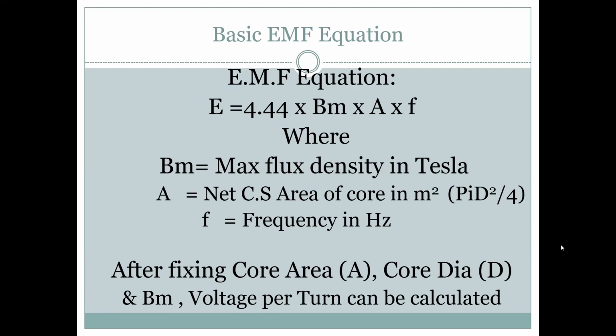Flux density is the maximum flux density in Tesla. This is for the core. A is the net cross section area of the core, that is pi d square by 4. After fixing the core area from there, because E, you know what excitation voltage you are going to give. You know because your consumer is telling you I want 1000 kVA at 33 by 11. So you know the details of the input.